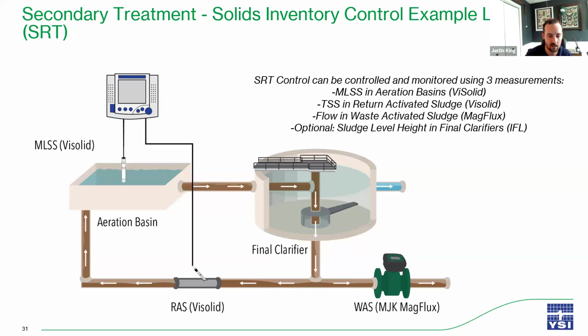And so with those two TSS sensors located, one in the aeration basin and the other in the RAS line, and then a final piece of instrumentation, a flow meter in the waste activated sludge line, we can really fine tune and control exactly how many bugs we're sending back into the aeration basin to maintain a healthy mixed liquor suspended solids, and how many of the bugs we're wasting away.